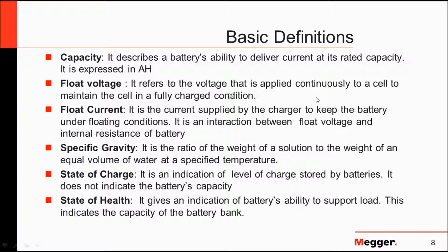As we go through this presentation, we'll be using some of the following definitions. Capacity describes the ability to deliver constant current at a rated rate, expressed in amp hours. Float voltage refers to the voltage applied continuously to a cell to maintain it in a fully charged condition. Float current is the current supplied by the charger to keep the batteries in a float condition, and is an interaction of the float voltage and internal resistance of the battery.